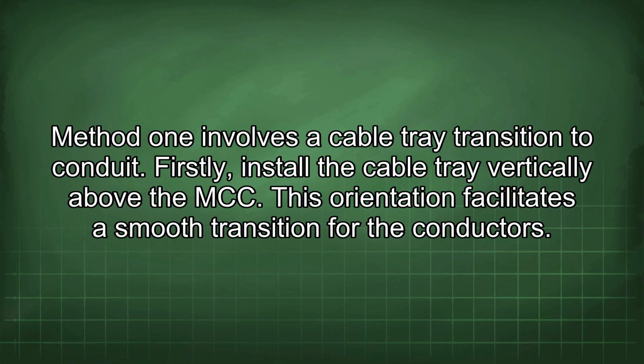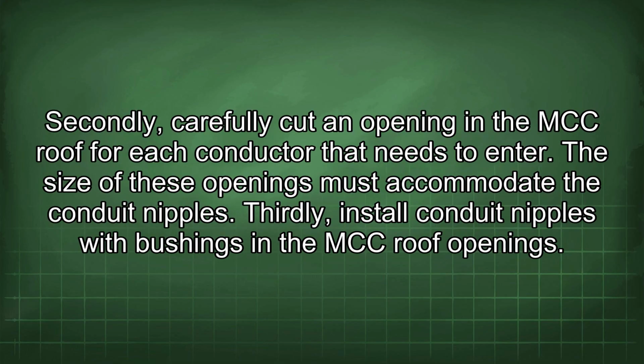Method 1 involves a cable tray transition to conduit. Firstly, install the cable tray vertically above the MCC. This orientation facilitates a smooth transition for the conductors. Secondly, carefully cut an opening in the MCC roof for each conductor that needs to enter. The size of these openings must accommodate the conduit nipples.